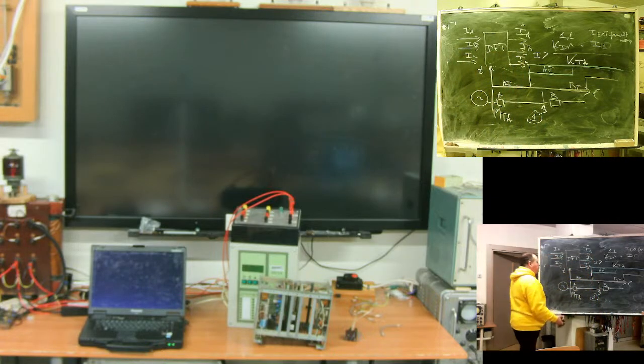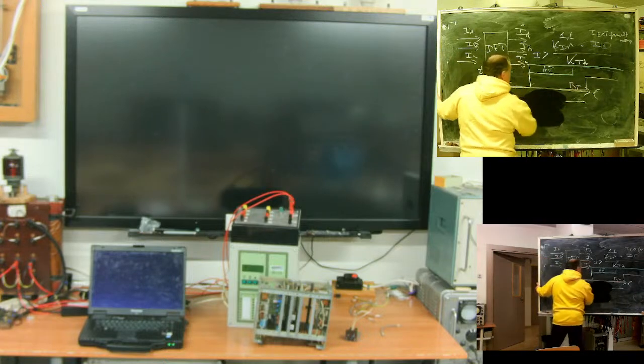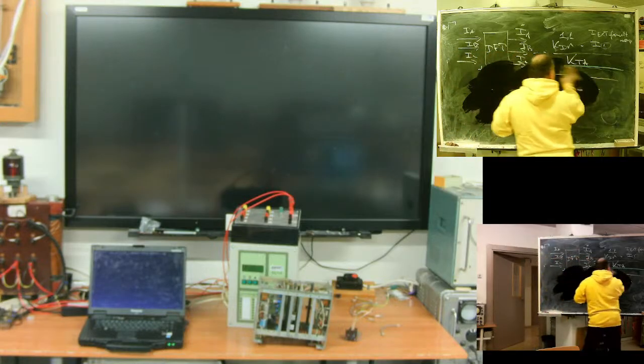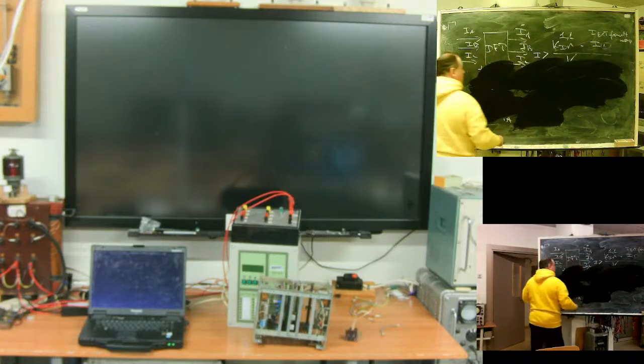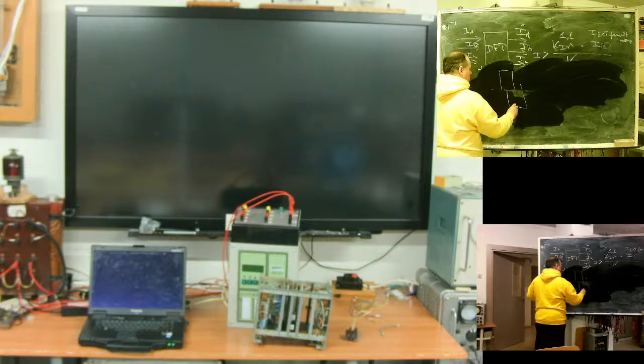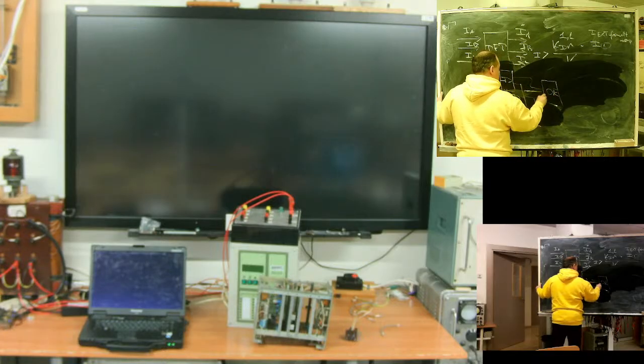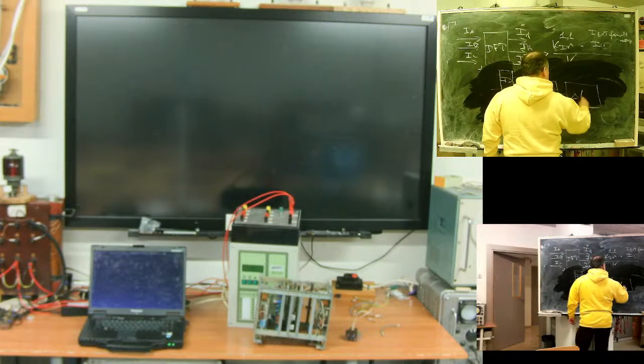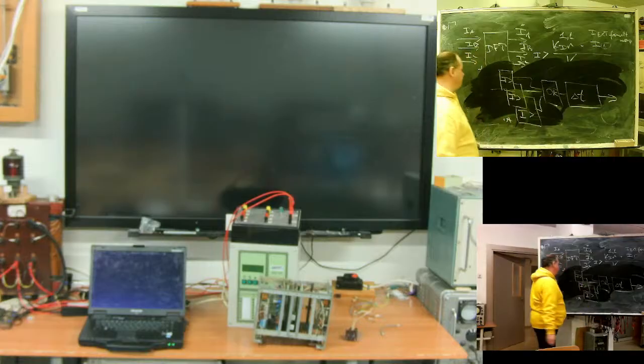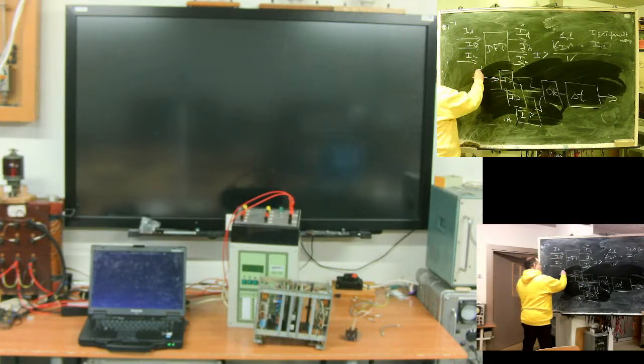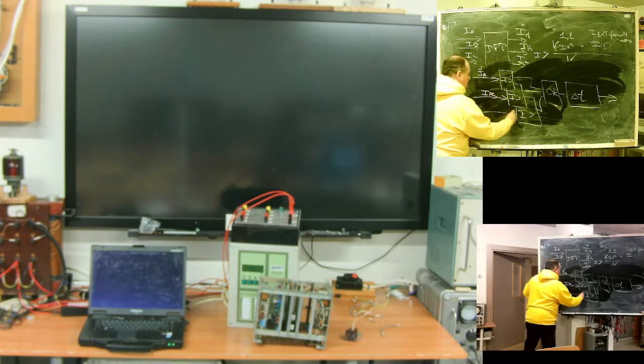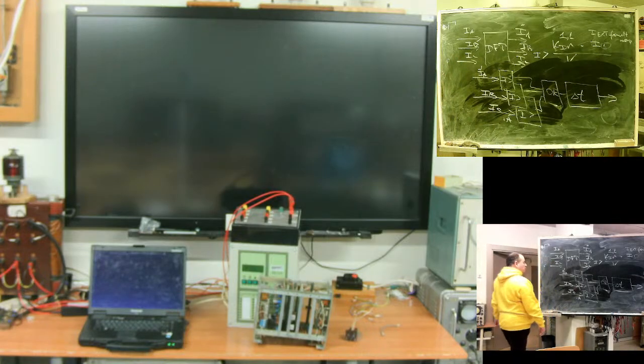In this case, what will be the setting formula? In the simplest way, current will be greater, or element, so trip of any activates the delay, and this is our signal. Here, A phase current, B phase. Okay, simple logic for the second stage. Simplified. This is simplified logic. In this simplified logic, what do we need?